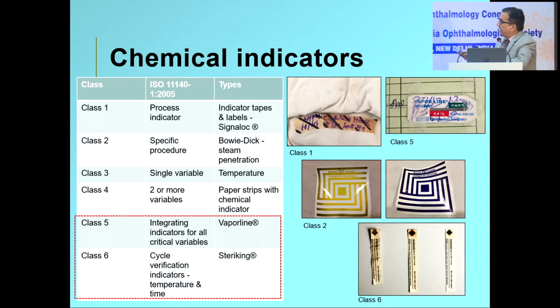that there is a gray line. If the gray line goes into the green zone, that is the pass zone, that means your sterile process is effective. And these are the class 6. So you need to have 1, this is mandatory, this is mandatory, and this. So this goes for each equipment, even a single pack of a swab or a reusable blade, you put this. This goes for the entire packet. So if you have a tray, you put this on it, and this you do once a day.